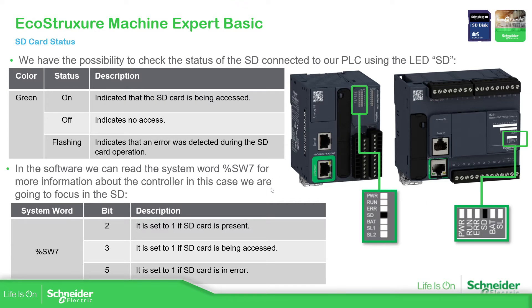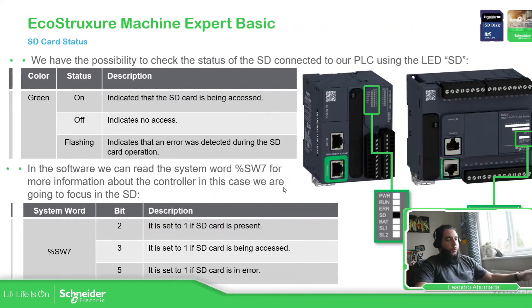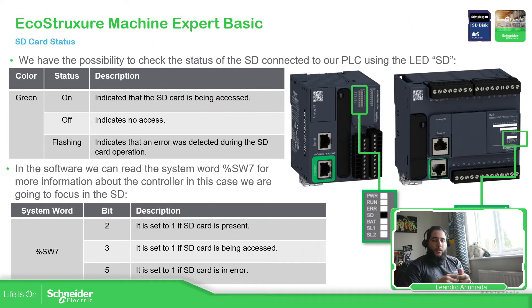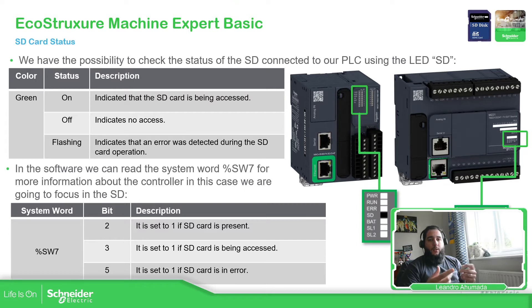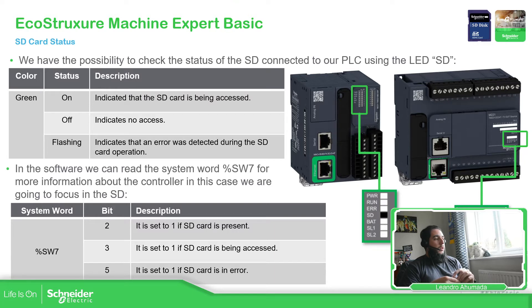If we want to do some logic inside the controller, we also have the possibility to use %SW7, which is one of the system words, to indicate if the SD card is present. For example, if you want to make a data log, it's good to know that the SD card is present to avoid mistakes or losing information. You can use it to trigger an error signal or whatever you need.